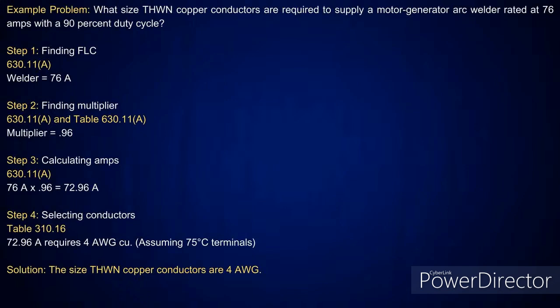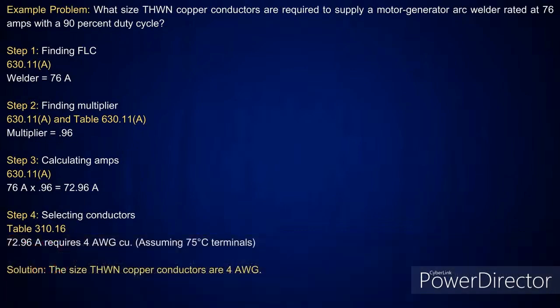I think we had a good comment come in that Danny mentions. The NEC gives you a direction to adjust ampacity if it's more than three current carrying conductors. So that's one thing you're going to have to really look at. Sure. And we actually did that in an earlier portion of this, probably about 3 or 4 episodes before. And I went through all that and explained it.